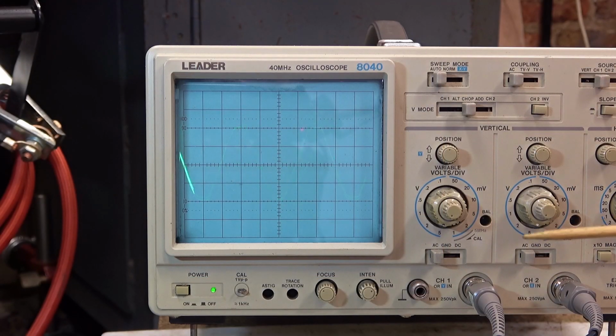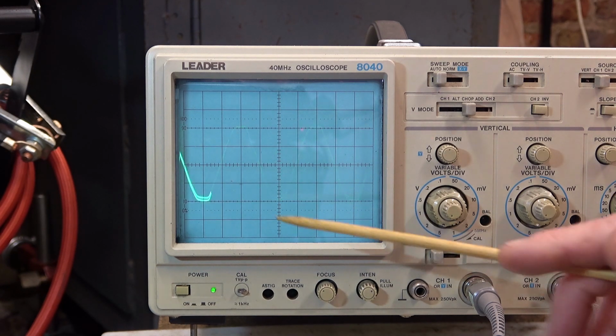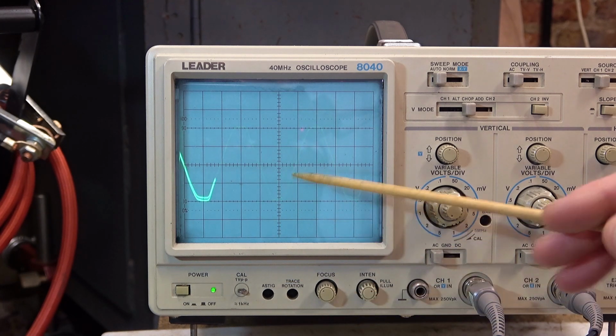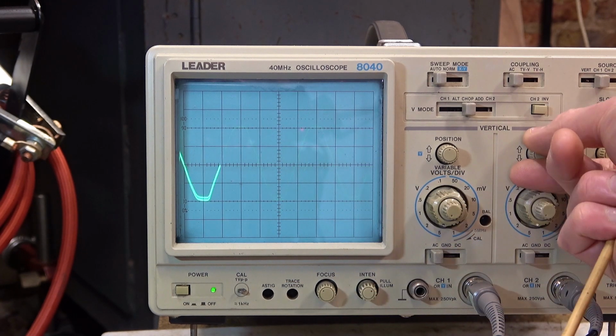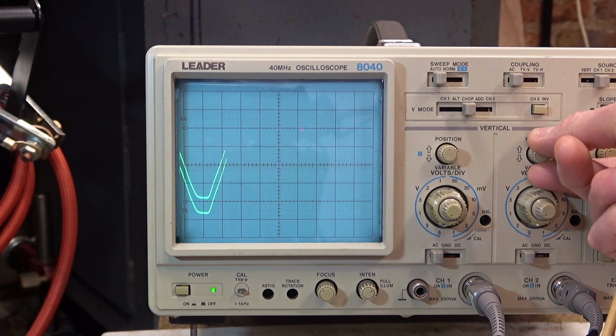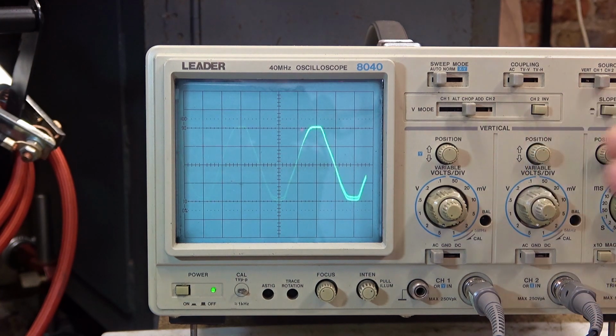Now, so far we've not seen any kind of initial pulse which is causing those relay contacts to pull apart the moment I press the contactor button. What I'd like to see is the voltage across L1 and L3. So these here are referenced to earth. It's giving us an idea, but it's not telling us the full story.